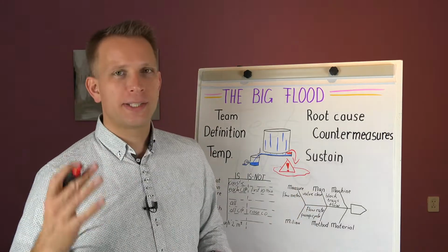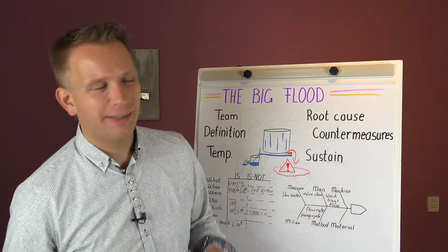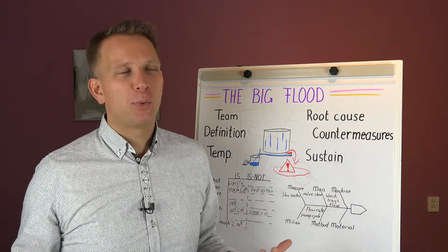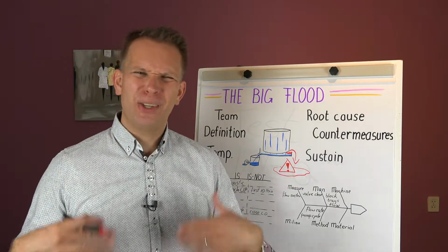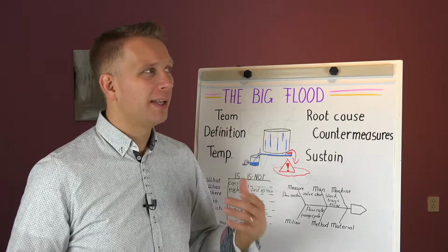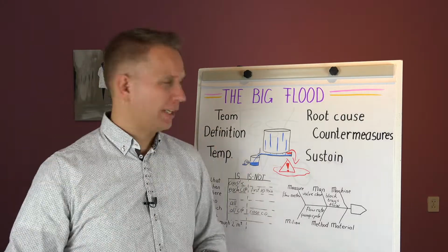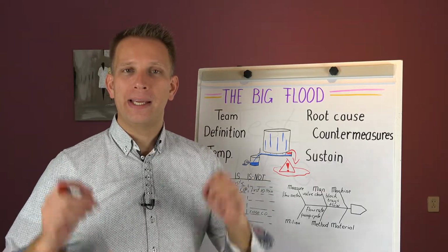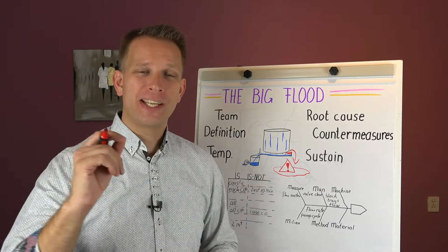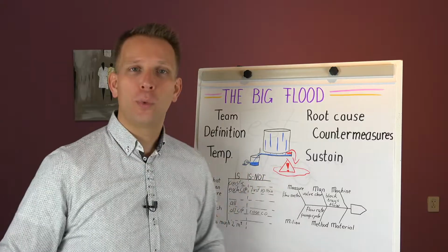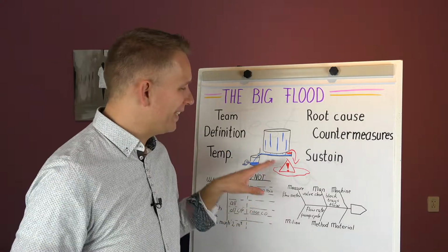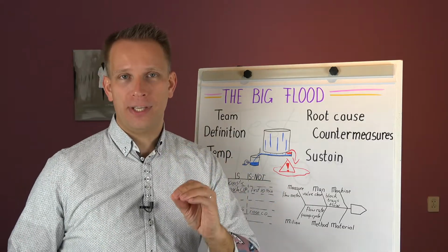Now why is it such a problem? If it would have been just water, it would still not be nice, right? You don't want any cleaning water running over the floor, but this is during an industrial cleaning cycle. So there is also a caustic phase and there is an acid phase, and this water is boiling hot. So this is a serious safety risk.